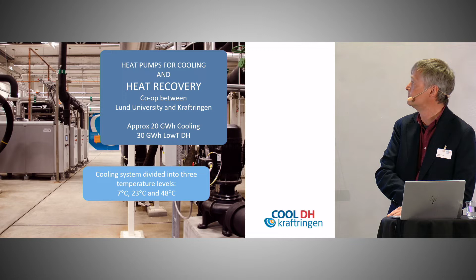Within the CoolDH project, we added equipment to provide heat to the local low-temperature grid. The equipment itself is rather basic, heat exchangers and pumps, but the control system is rather complicated. We can vary the output temperature from the heat pumps depending on whether we want to put the heat into the low-temperature grid or also into the ordinary district heating grid.